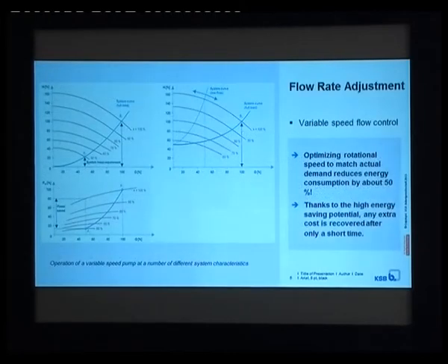More with this variable flow or variable speed, with the affinity law, simply changing a small frequency or little speed of the pump, we can get very high energy savings.